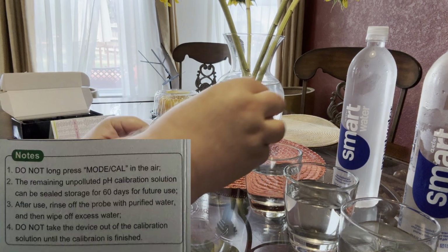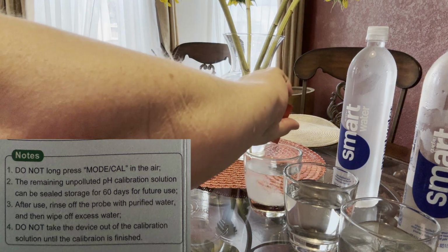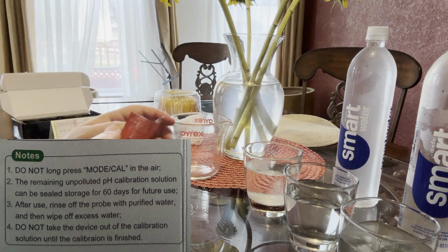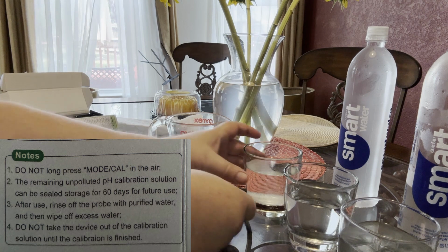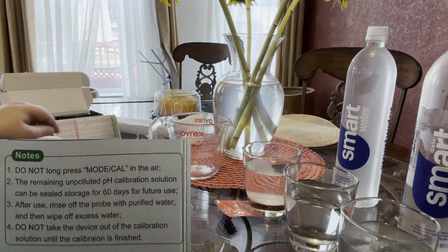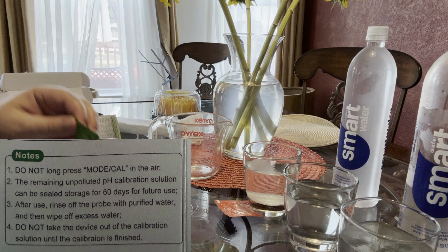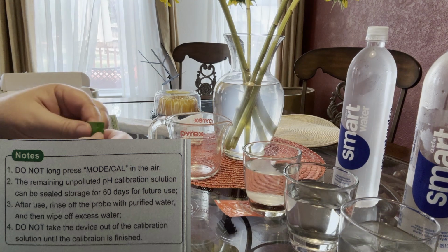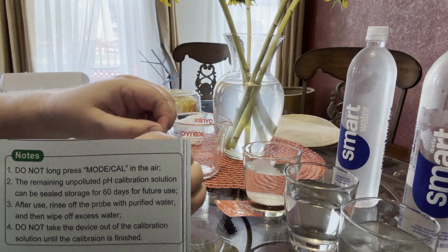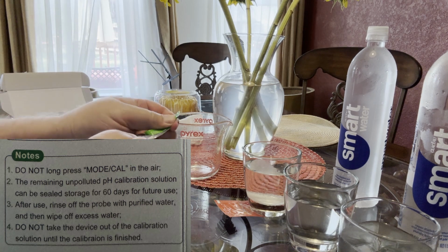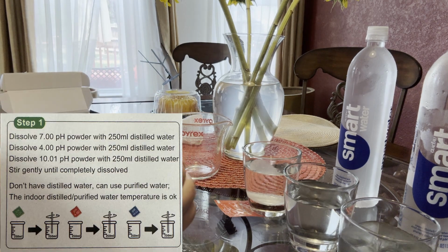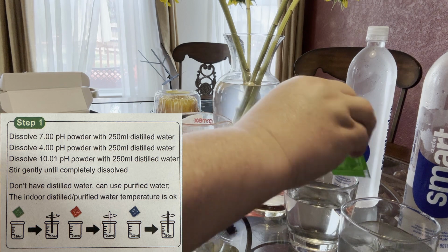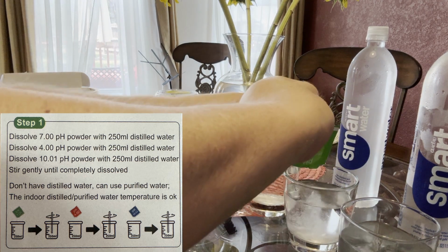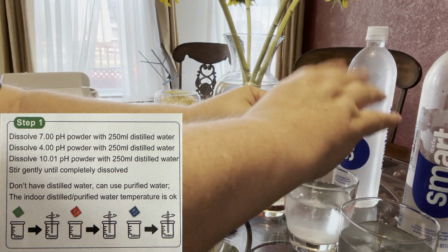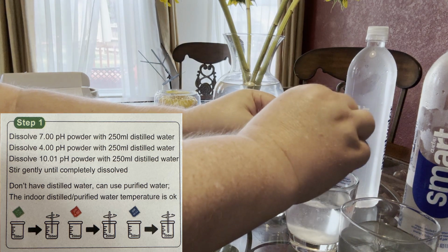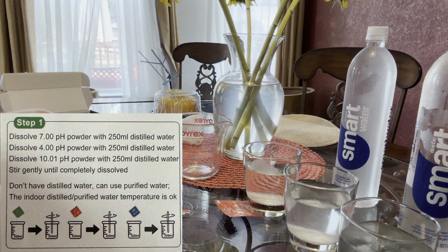Do not long press the mode cal button in the air. This may make the meter unusable. Do not take the device out of the solution until the calibration is finished. The pH number will stop flashing when finished. Lastly, rinse the probe between calibrations so you don't contaminate the other solutions. Step 1. Dissolve the packets of pH powder, 1 each, into the 3 containers of 250 milliliter water. In my case, I had to wait about an hour for the powder to completely dissolve.